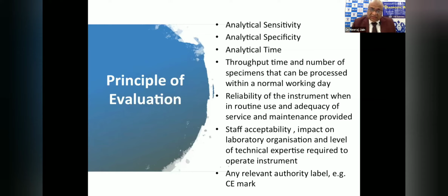Suppose there are 3 machines testing glucose. One machine gives 100, 110, 120, 130. The second machine gives 101, 102, 103, 104. The third machine gives 100.1, 100.2, 100.3, 100.4. In the first case, the minimum difference appreciable is 10. In the second case, it is 1. And in the third case, it is 0.1. So analytical sensitivity is best in the case of the third machine. But we have to see practicality also, whether it is really useful for us or not. But we should know all these things when we are evaluating a machine.